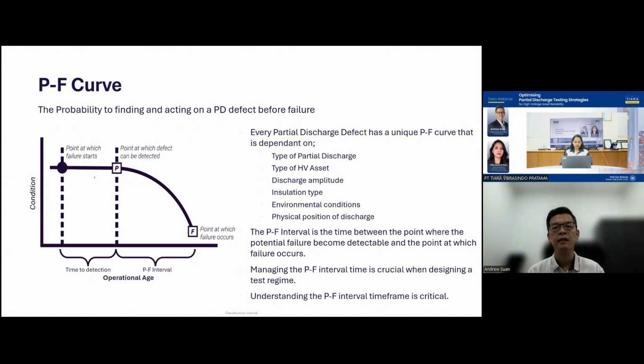Also, some brands and certain models of switchgear that I have come across are known to cause more problems in certain compartments. In Singapore, there is a certain brand whose VT always has problems. So every time we go in, the first thing we check is whether it is this ABC brand. Then I will ask my engineer to please check the VT first, because 9 out of 10 problems always come from the VT. So knowing the type of HV asset is also very important.